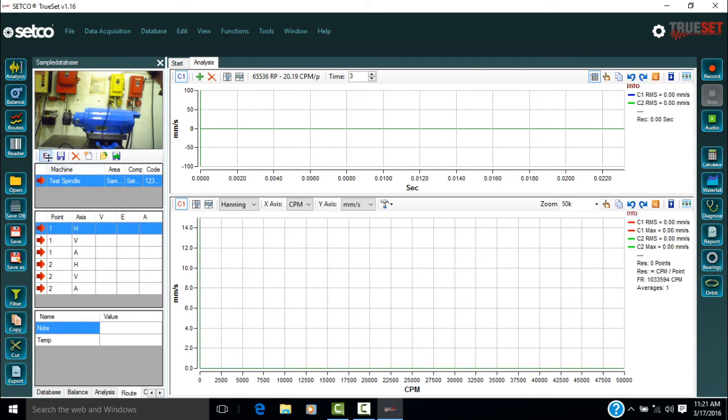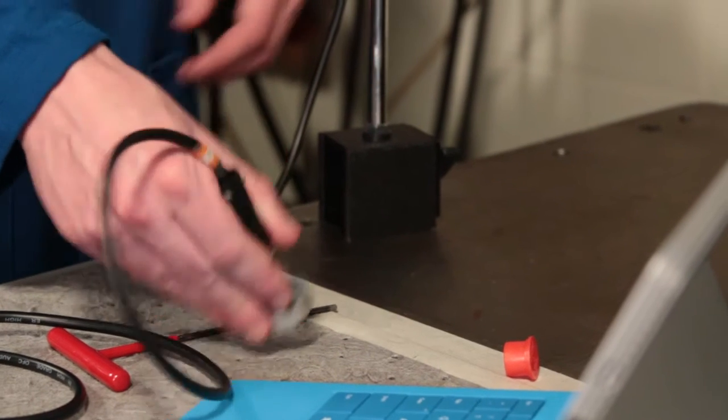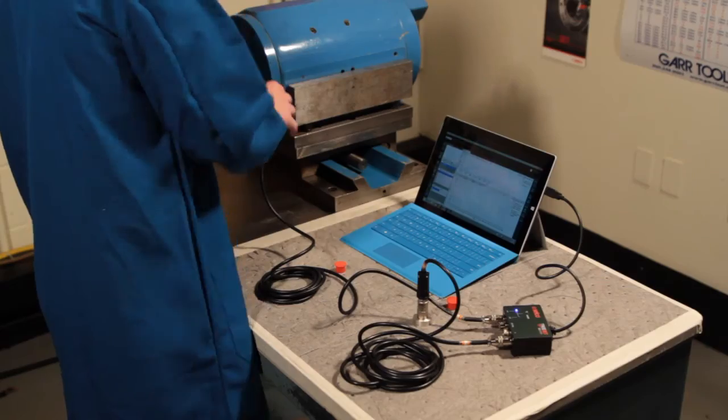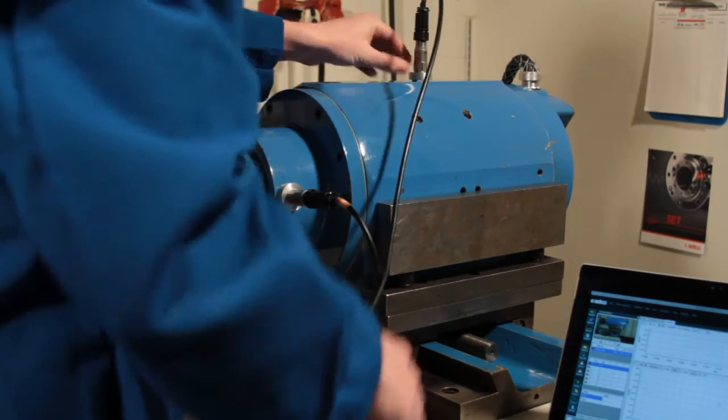If using the reference accelerometer, select the F button to activate it. The first accelerometer is placed in the horizontal position over the bearings to match the first axis in the route. This data will be taken first. Then, place the reference accelerometer anywhere on the equipment's body. This accelerometer cannot move from this position. Run the equipment at its typical operating RPM specified when entering equipment into the database.